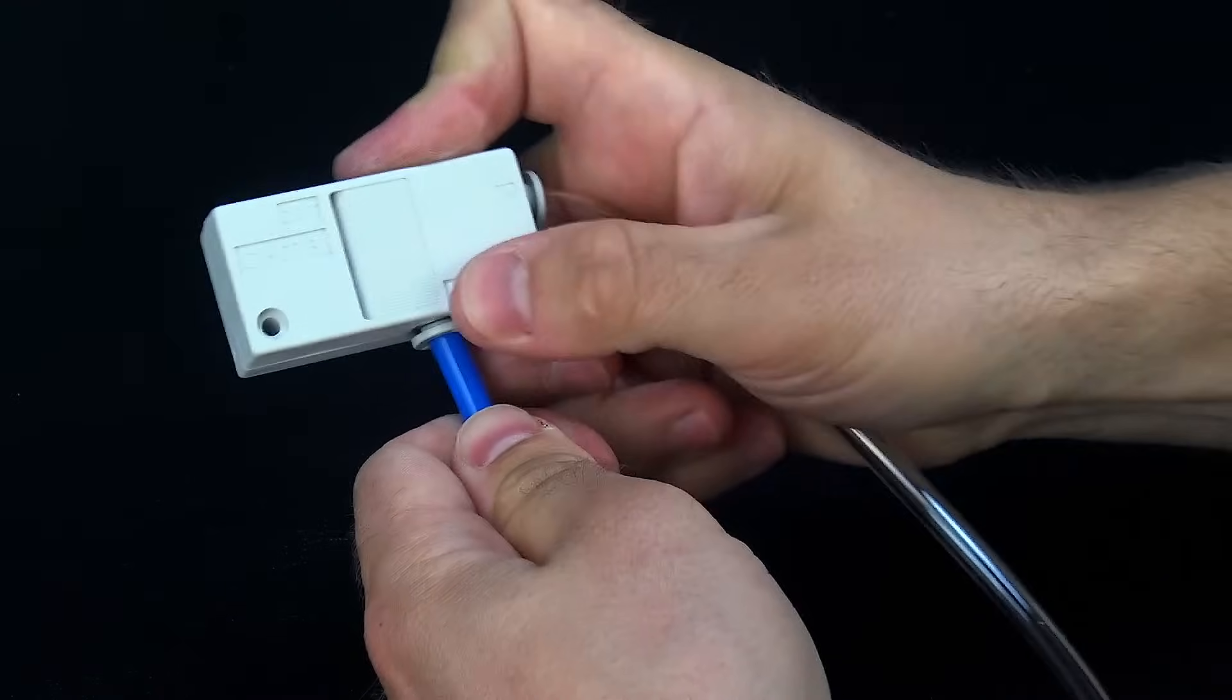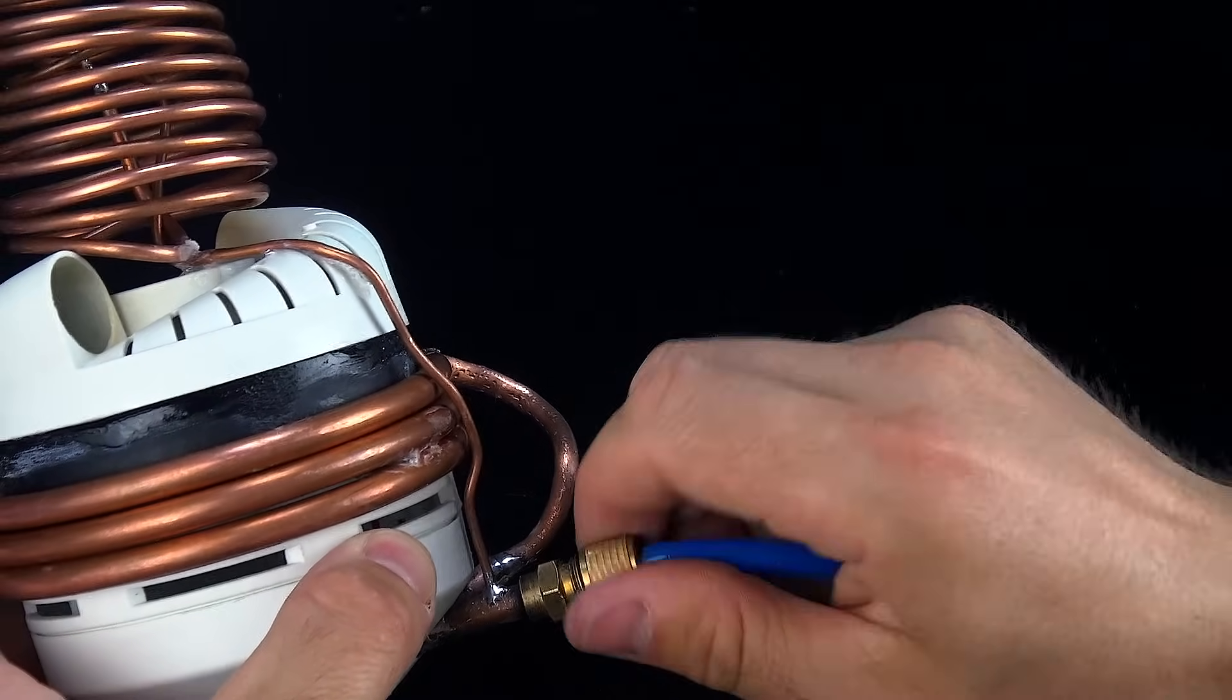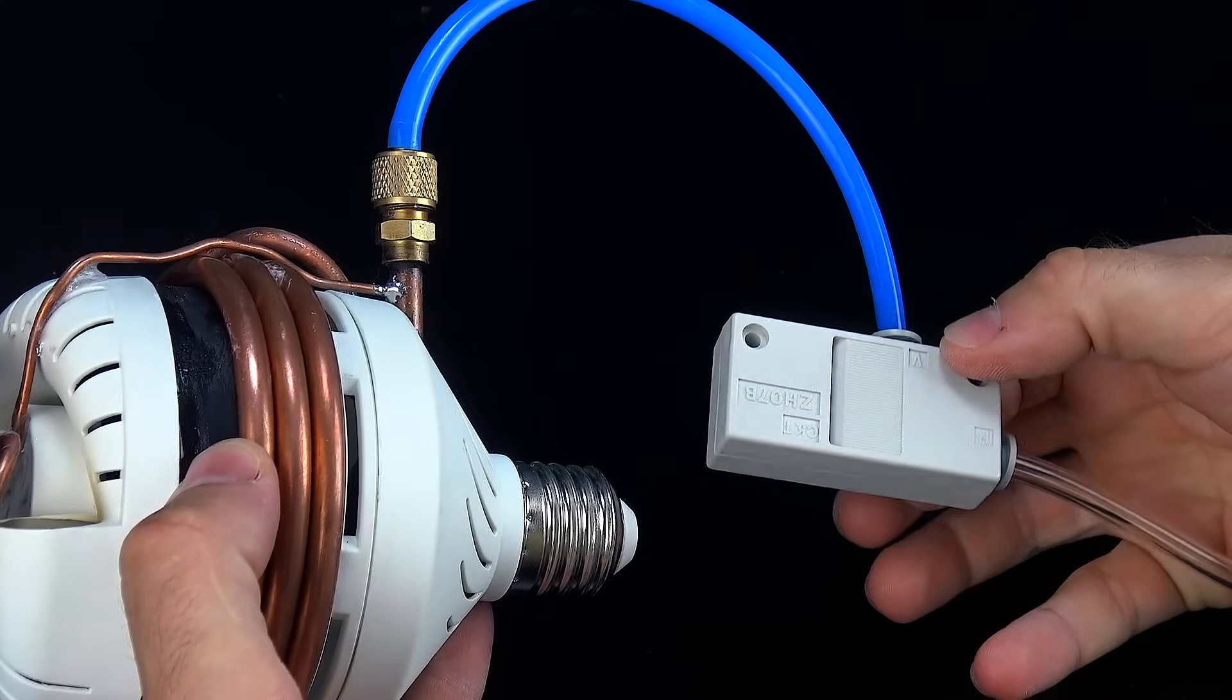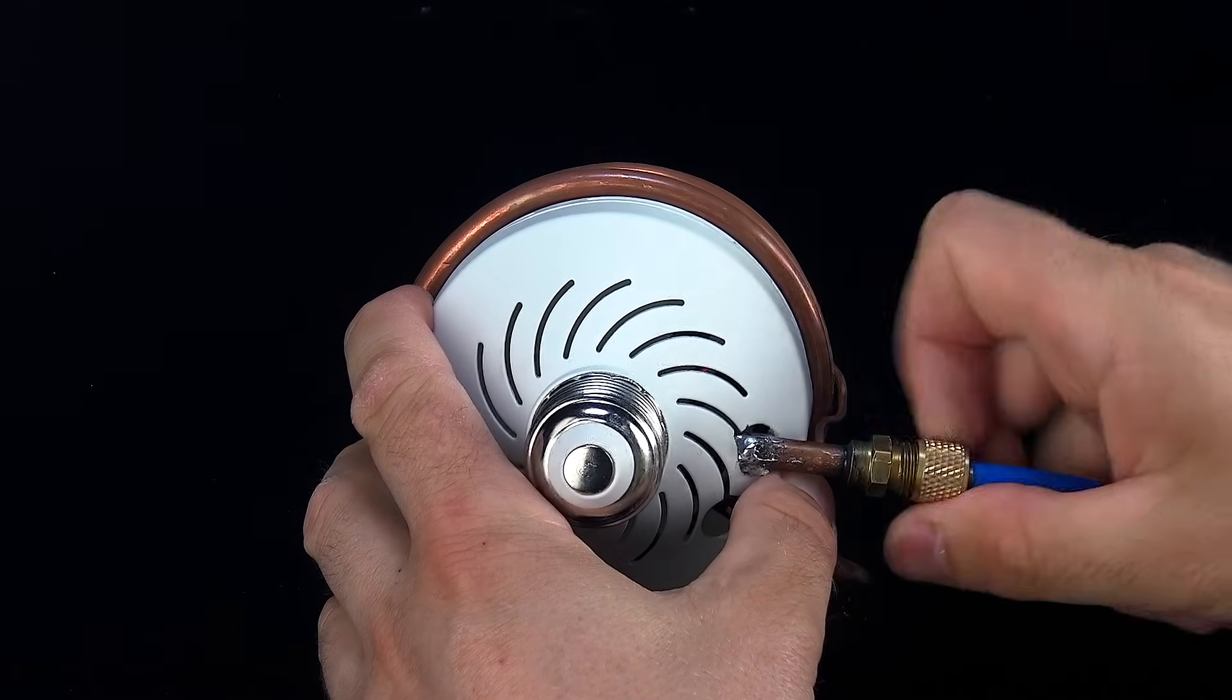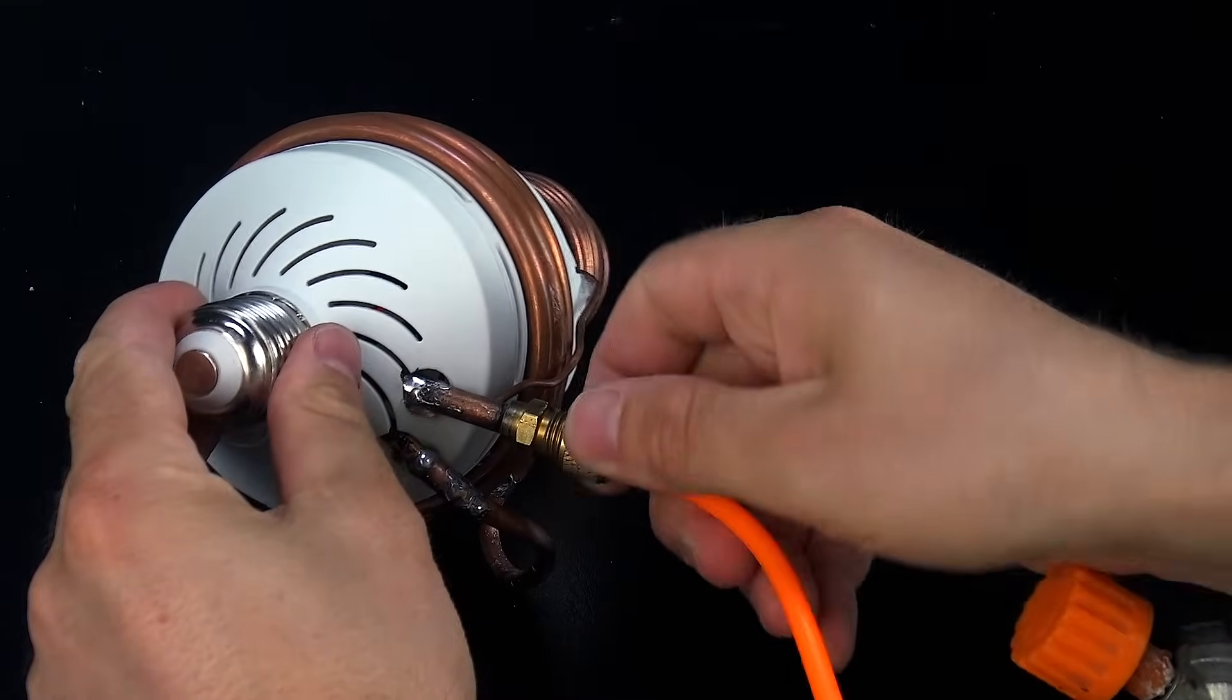We're almost at the finish line. With the vacuum generator and compressor set up, it's time for one final but very important step: vacuuming the system. This process removes all the air and any remaining moisture inside the system, which could interfere with the refrigerant's performance. Plus, creating a vacuum allows us to add more refrigerant into the system, improving both efficiency and reliability. So yeah, vacuuming is absolutely essential. Think of it like taking a deep breath before getting to work: clean, dry, and ready to run.